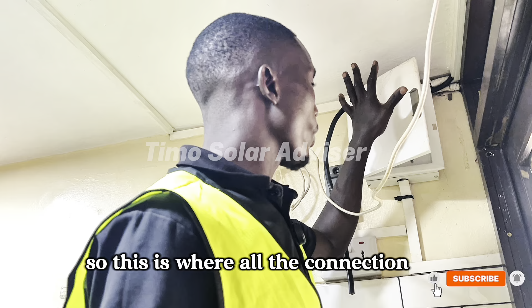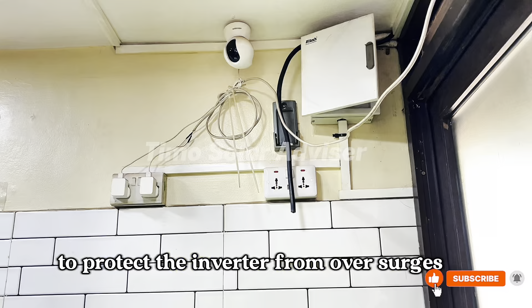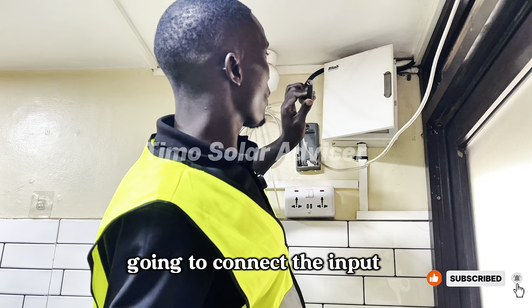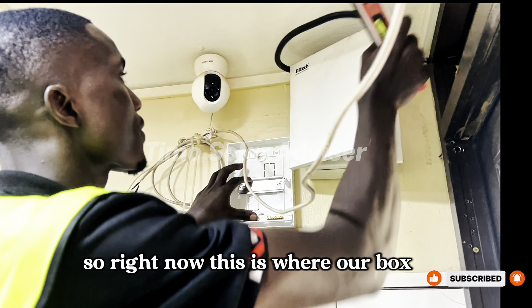Still, this is an SPD. Also, it's going to be connected together with this breaker. This one is going to help us to remove any surge which is going to the inverter, to protect the inverter from over surges. This is the box where I'm going to put these two breakers, the AC breaker and the AC SPD. So right here, this is the cable where we're going to connect the input, also the output from the inverter. So we are planning to put this box here because we want to be close to this main switch. So right now, this is where our box is going to be placed.